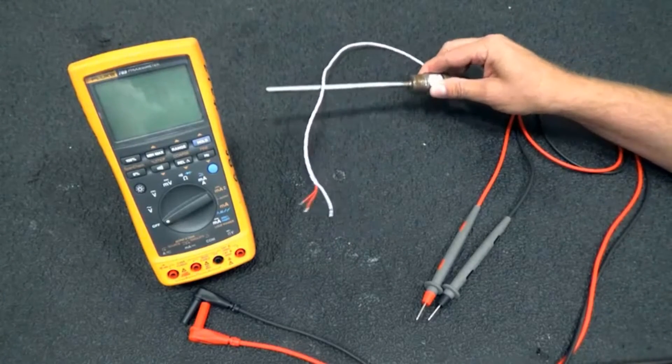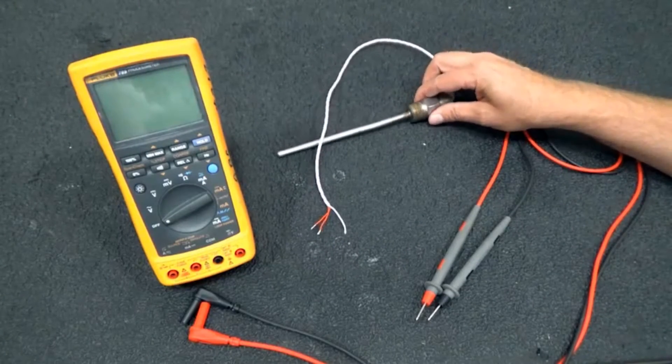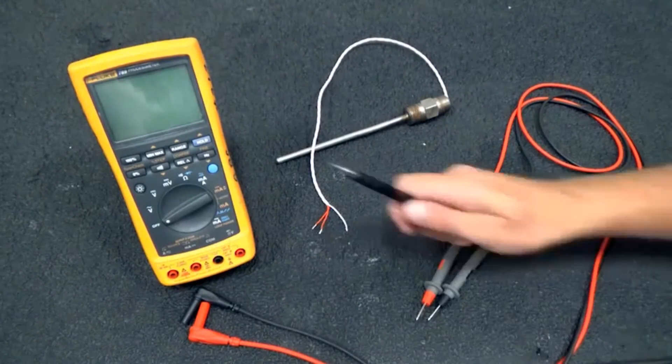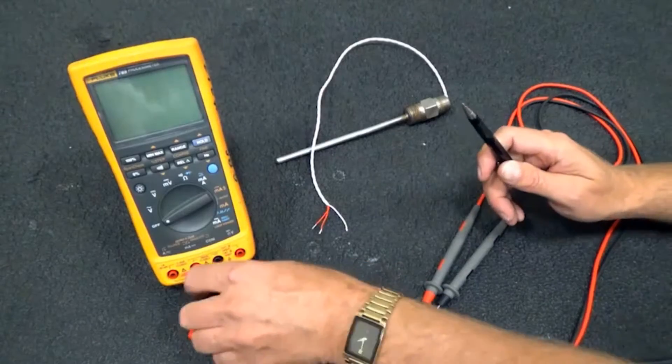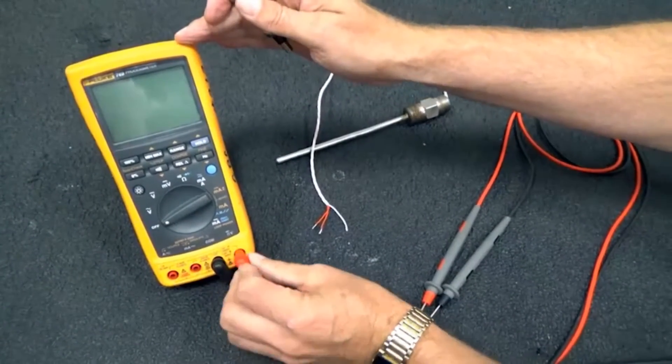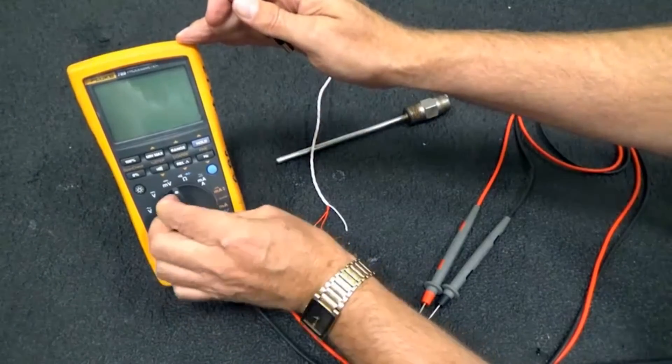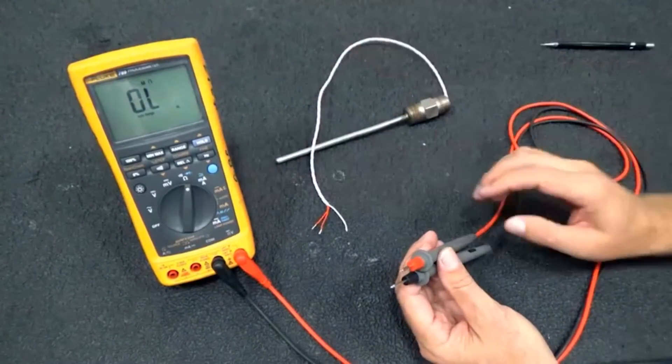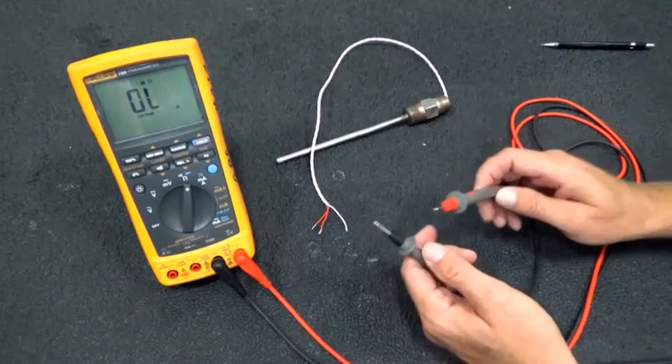We want to measure the resistance of this RTD, so we want to measure ohms. You can see that ohms is shown right here, so we're going to plug the meter into the common and we'll plug into ohms here, and I'll go ahead and turn it on to ohms. We see we're reading in mega ohms, we have an open circuit, which is what that means.